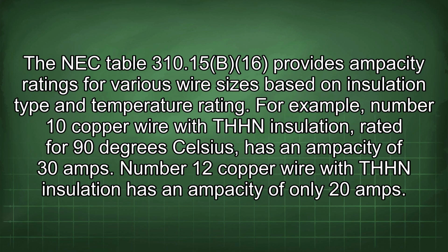The NEC Table 310.15(B)(16) provides ampacity ratings for various wire sizes based on insulation type and temperature rating. For example, number 10 copper wire with THHN insulation, rated for 90 degrees Celsius, has an ampacity of 30 amps. Number 12 copper wire with THHN insulation has an ampacity of only 20 amps.